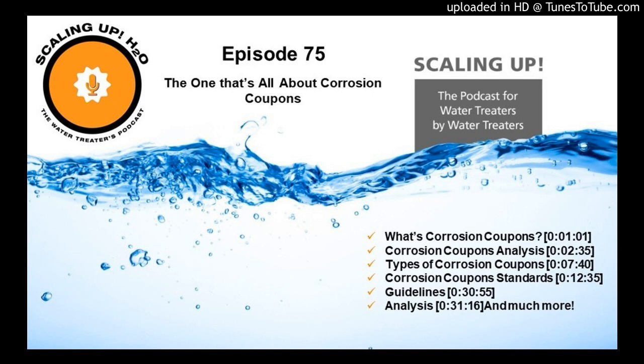Now, there's a lot of confusion with corrosion coupons about which coupon to put first. And here is the way you should put 4 different metals in a corrosion coupon rack, starting from the bottom. And again, flow is coming from the bottom, going through the corrosion coupon rack, exiting through the top. So you would start with aluminum. You would then put in mild steel. You would then put your copper in, and then finally you would put your stainless steel. Now, for most of you, that's all you needed to know, and you're probably just going to be using mild steel and then copper. So you would put the mild steel in first, the flow would hit that, go up, hit the copper, and then it would go out of the system.